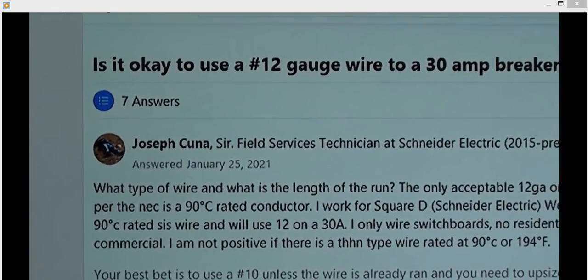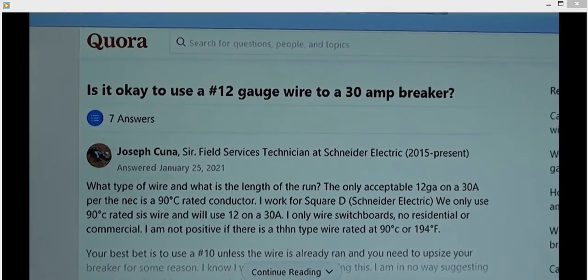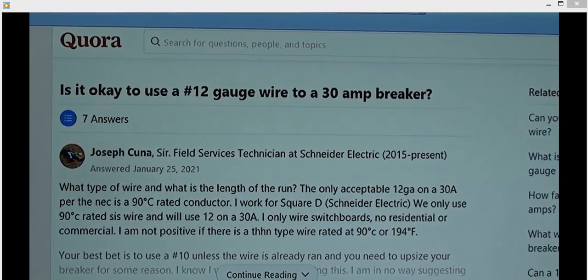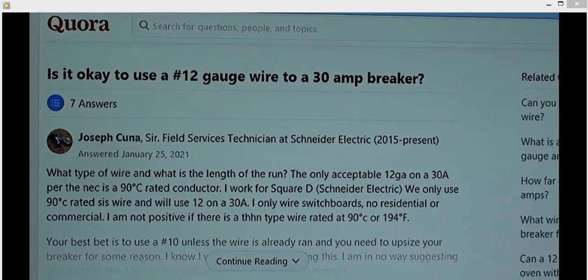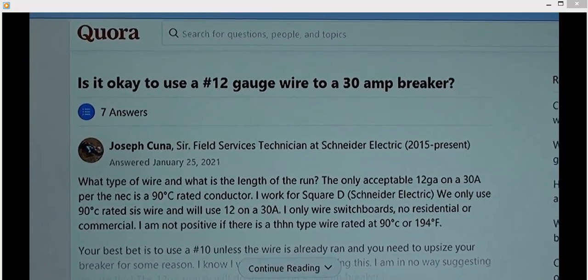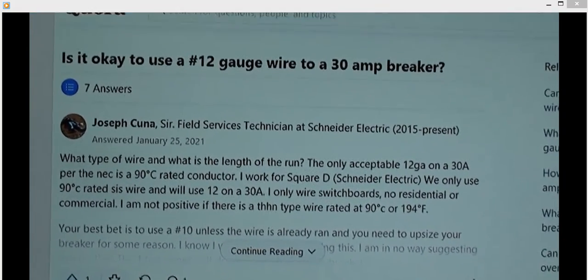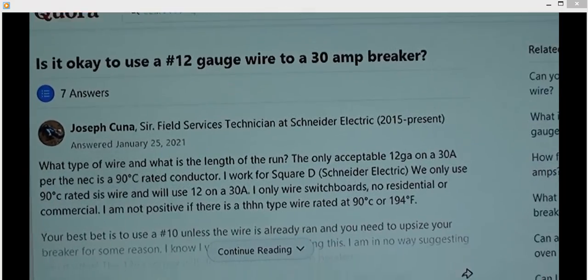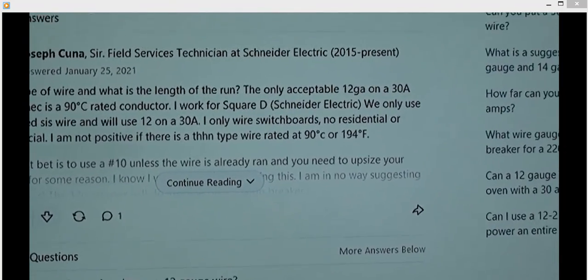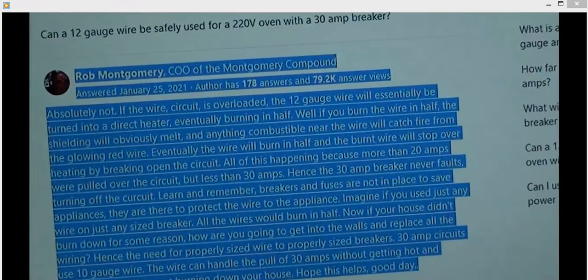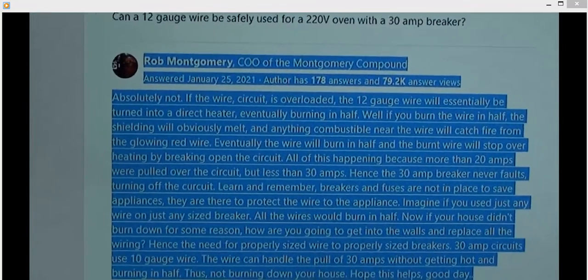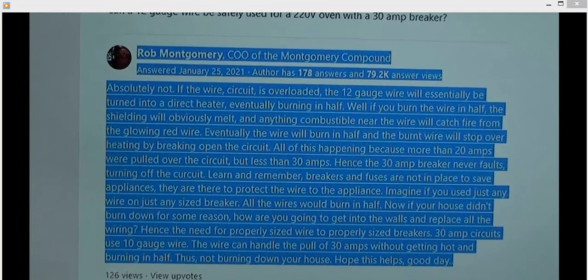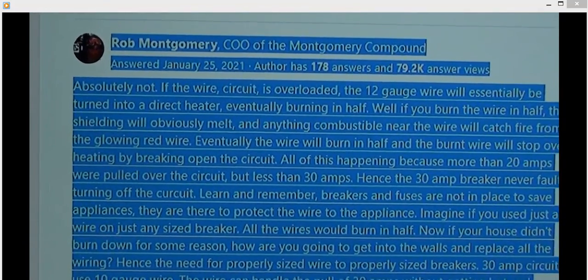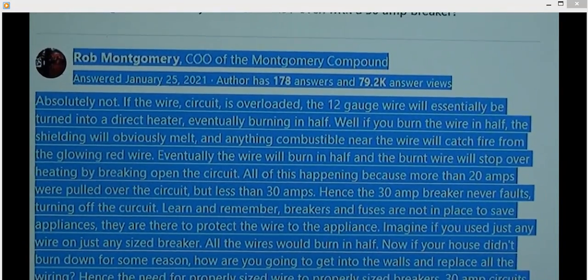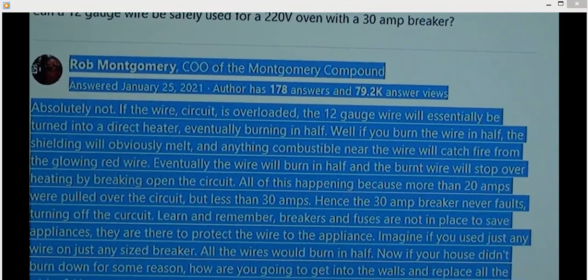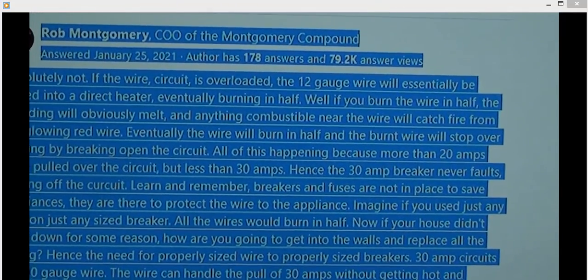So I went on to Google. Is it okay to use a number 12 wire gauge to a 30 amp breaker? And we go down to the guy that answered it. Whoops. Absolutely not.